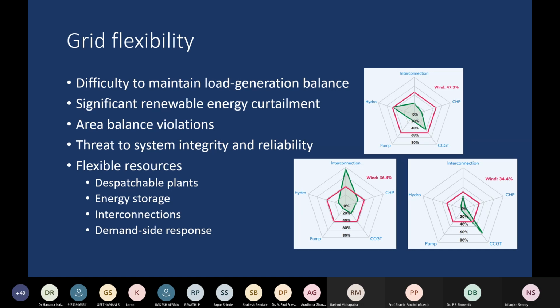The third problem comes from area balance violations. For instance, when you have two areas which have a certain contracted power exchange, for example, area 1 has contracted with area 2 for a power exchange of, let's say, 500 megawatts. Now because of renewable energy variations, the wind does not blow, and so instead of transferring 500 megawatts, area 2 is maybe transferring 400 megawatts. That means there is a violation of the area balance, and these kinds of violations are expected to be sustained and very frequent as more and more renewable energy becomes integrated into the grid.